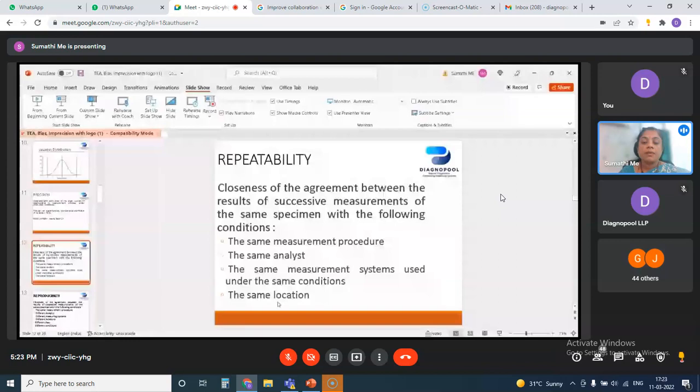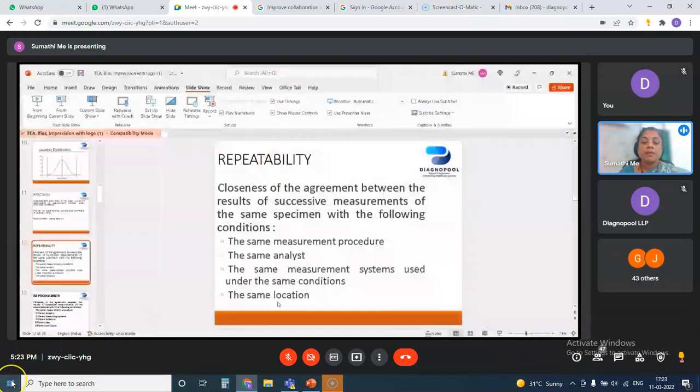Or you have something called the peer mean. The people who are using controls such as Bio-Rad have a system called Unity software. The Unity software captures the internal quality control data from various locations and derives the peer mean on a real-time basis. So this mean can also be taken as the peer mean. This mean is more appropriate because the peer mean is set for a particular lot number, a particular reagent lot number, so it should suit your system as well as that particular lot number.